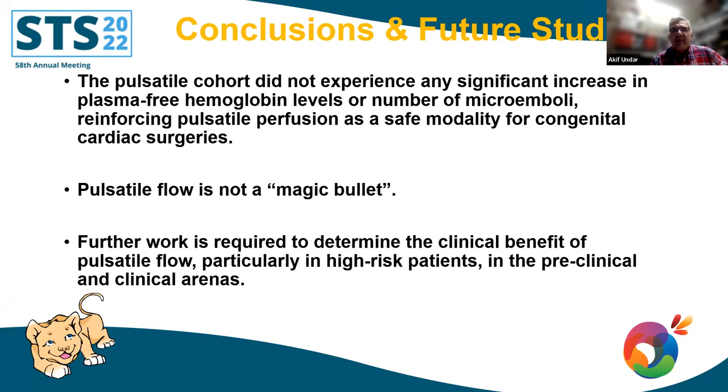stratified groups. But at the same time, in this clinical trial, I believe that this is one of the rare ones, in particular among pediatric trials, maybe the first one, showing that the plasma-free hemoglobin levels were not different, pulse versus no pulse. And more importantly, microemboli levels at the middle cerebral artery, as well as in the circuitry, were very similar, pulse versus no pulse.